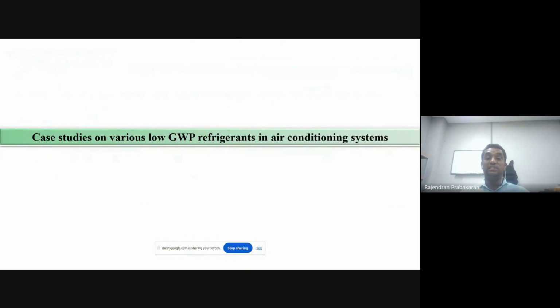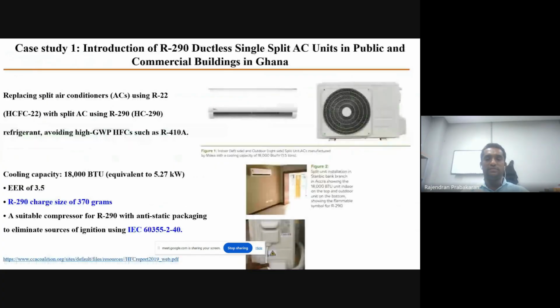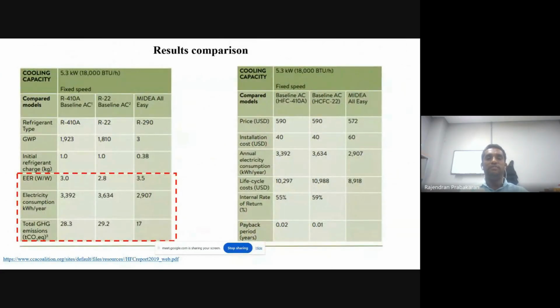Next, we can see some case studies. They have implemented different low-GWP refrigerants in building cooling applications. The first study was conducted in Ghana. They used a ductless R290 system with a capacity of 5.27 kilowatts, and they followed the same IEC 60335 standard with an anti-static packaging arrangement for the compressors. They compared the performance with R22 as well as R410A. We can see both tables: the first indicates thermal performance, and the second is all about cost and economic viability.